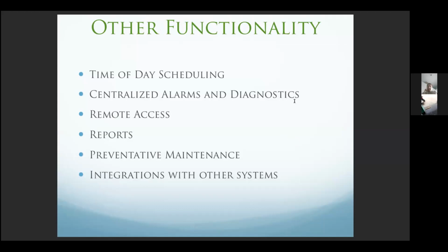Some of the other things you can do with the system level controller are time of day scheduling. So you can put all your equipment or your systems on a schedule. You can tell it, going back to the same example, the office building's going to start getting occupied at 8 a.m. So we want to make sure all the equipment is running by then, set points are achieved by then, so we can schedule it that way.